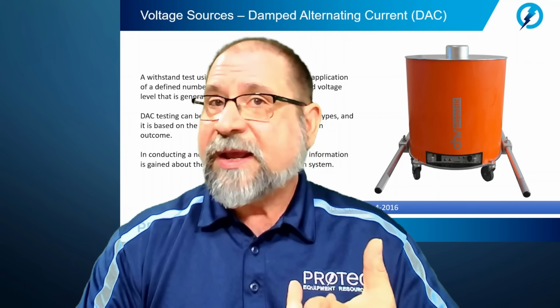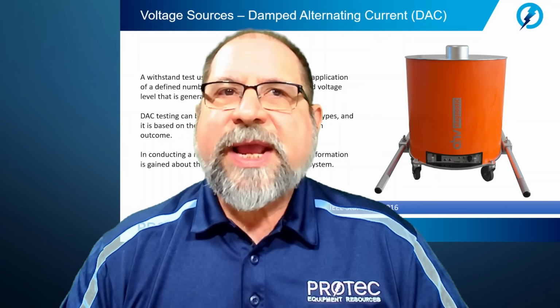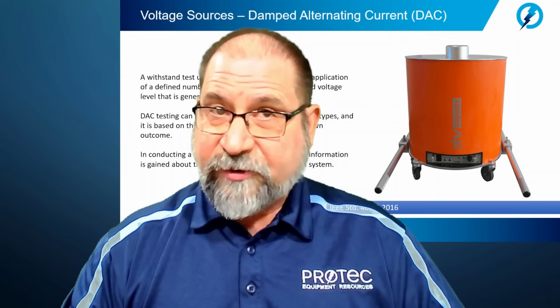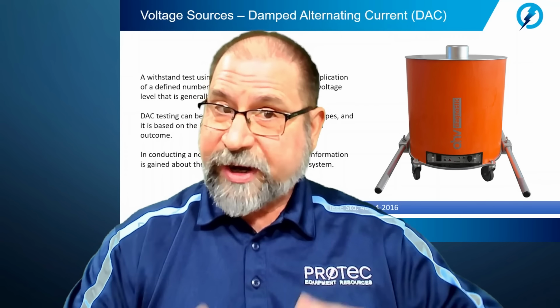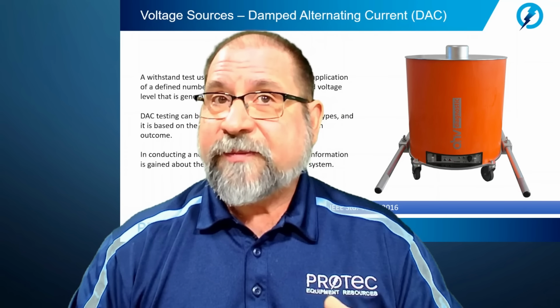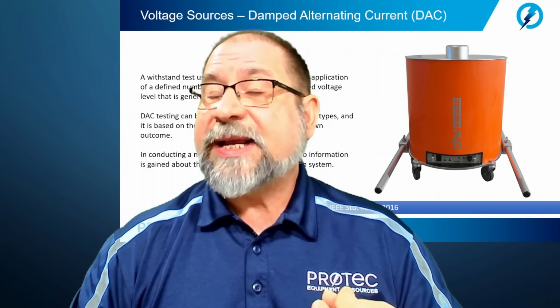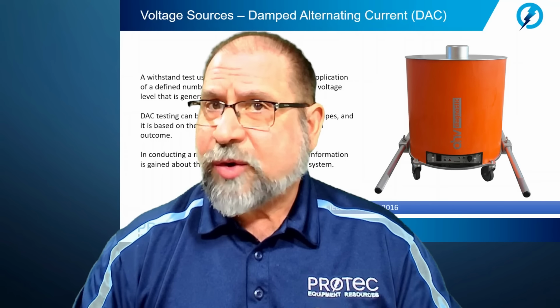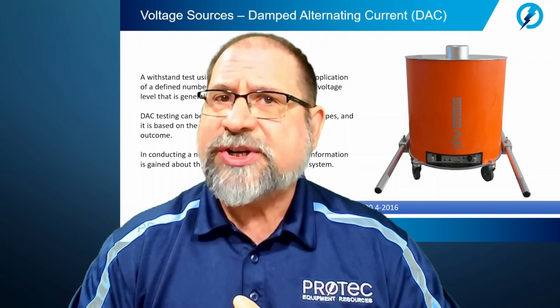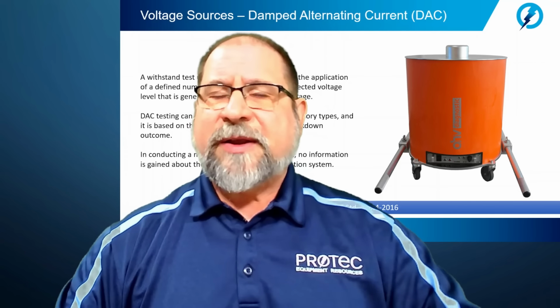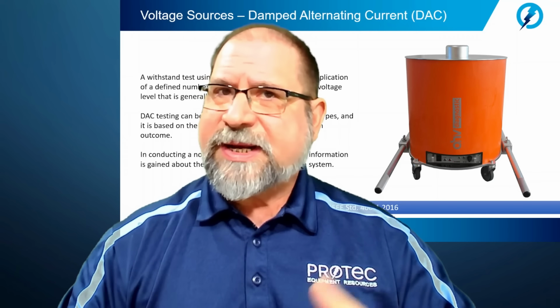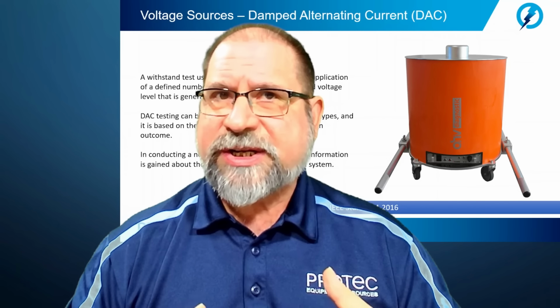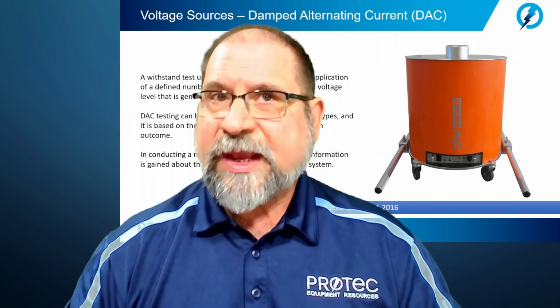In a monitored withstand test, we are looking at other aspects. For instance, maybe we are monitoring the occurrence of partial discharge. Does partial discharge occur? At what time into the test does the partial discharge occur? What is the amplitude of the partial discharge? So here we see that we have more data other than just a time-based test.